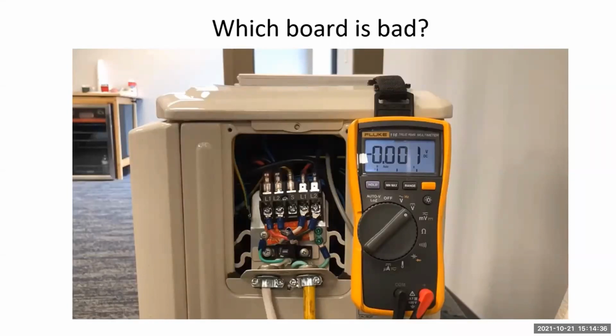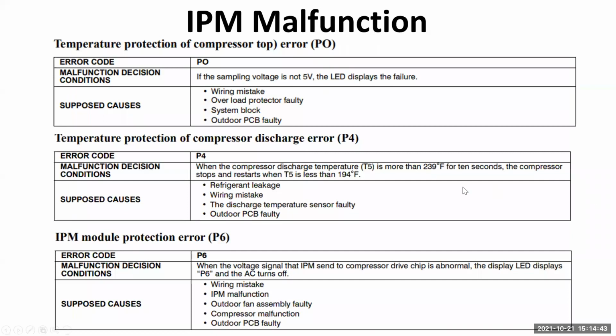Now, obviously, we don't want to do that 100% because that way is wrong. We're going to check them other ways. And I'll get to that in a little bit further in here. So you got the P0, P4, and P6 codes also. This is for the outdoor board. The IPM, you want to check continuity on it. If you got one of these with the P in them, you obviously want to go outside because that's usually where the P codes originate.